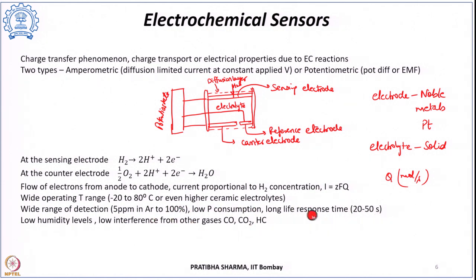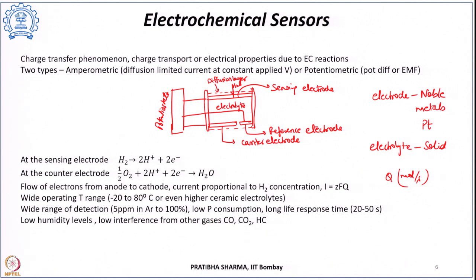A major challenge is that these sensors should be subjected to low humidity levels, and interference from other gases like carbon monoxide, carbon dioxide, and other hydrocarbons should be minimized. The potentiometric electrochemical sensor measures the potential difference or EMF between two electrodes under zero-current conditions, with the electrode potential calibrated to hydrogen gas concentration.